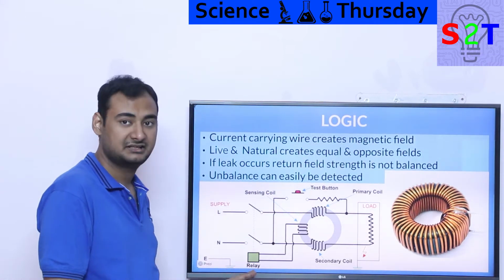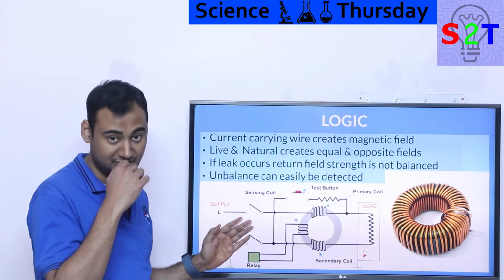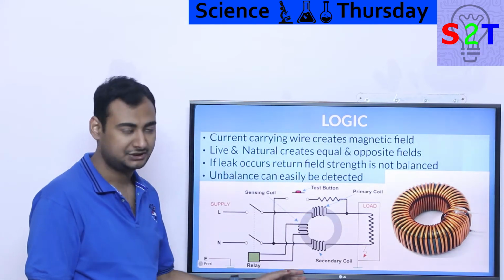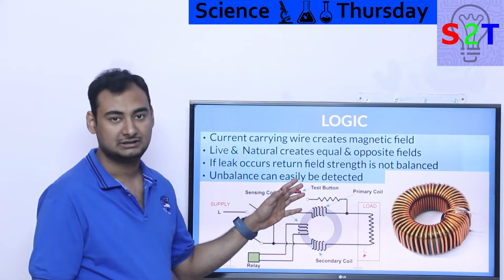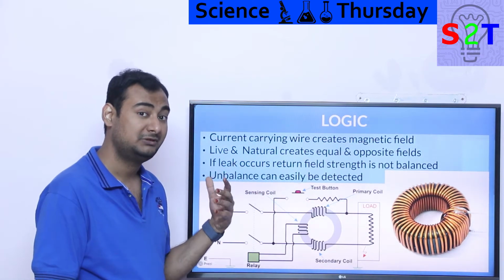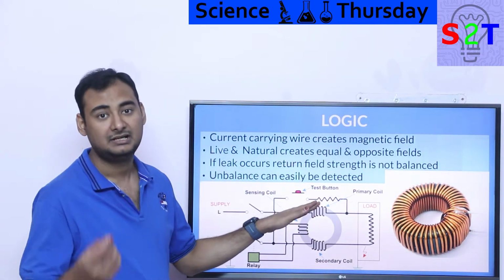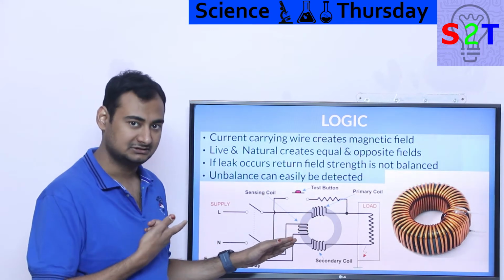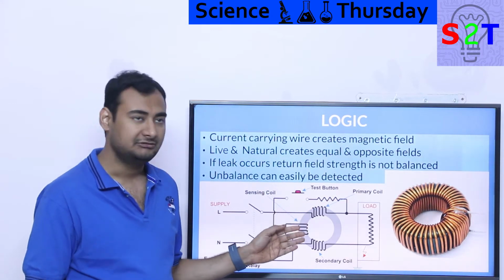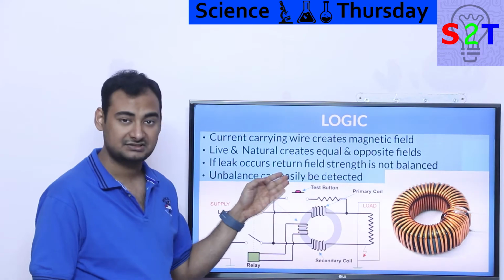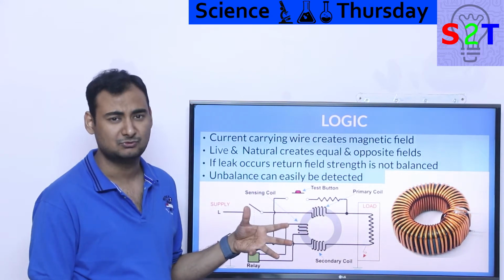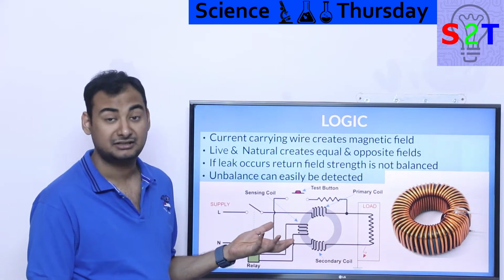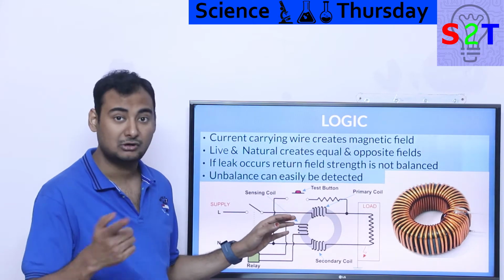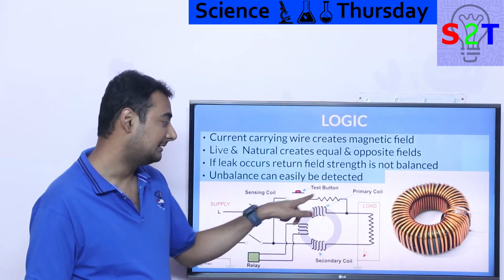The moment unbalance is detected, it triggers a relay and cuts the connection because it assumes that you have a fault connection. Now, there is generally also a bypass system that allows it to be tested. So you will have a resistor fine-tuned for the value that the breaker is designed for. Let's say if the breaker is designed for 30 milliampere, you will have a resistor fitted to that. If you have a breaker that is a bit less sensitive, let's say 100 milliampere, the resistor would be a bit bigger to accommodate that, and then that would be directly bypassed through the primary coil.